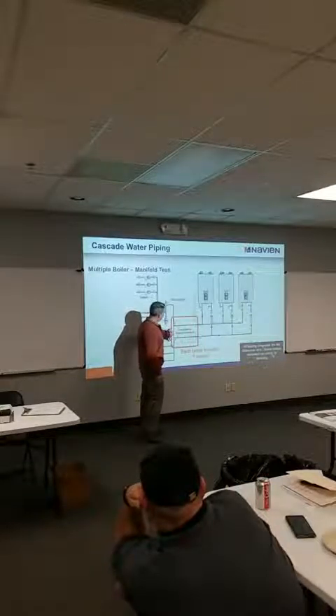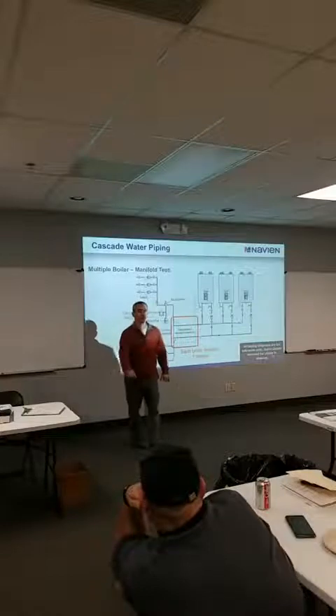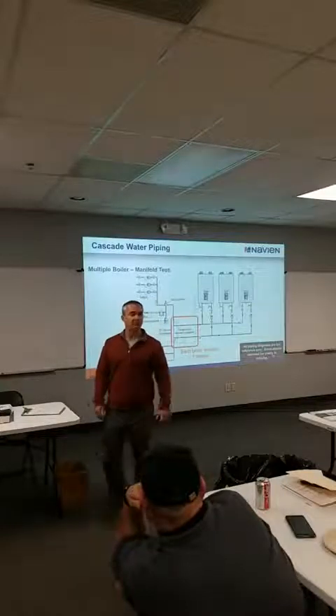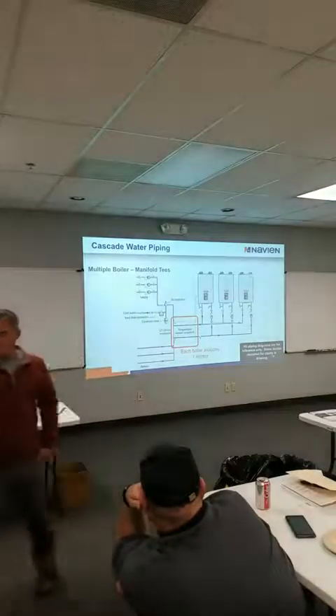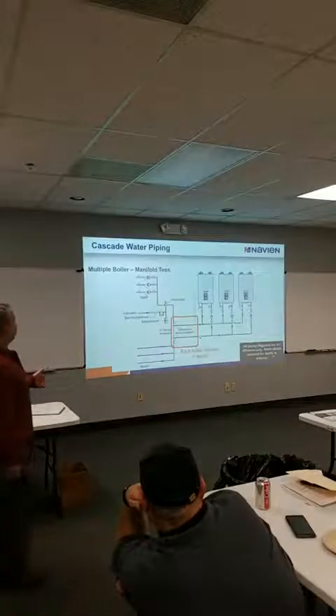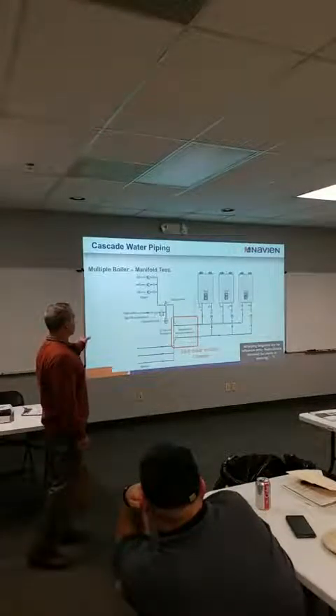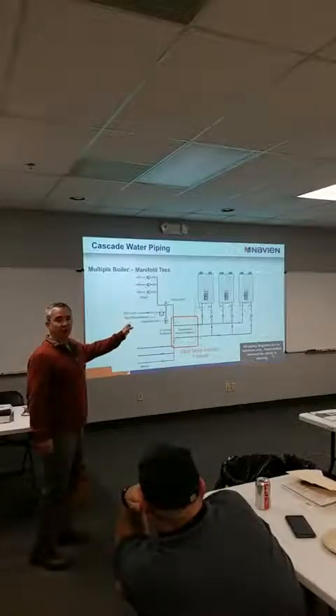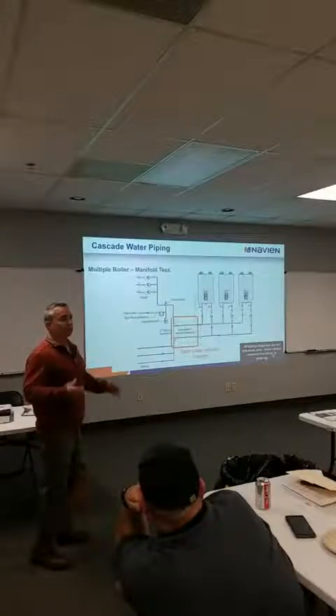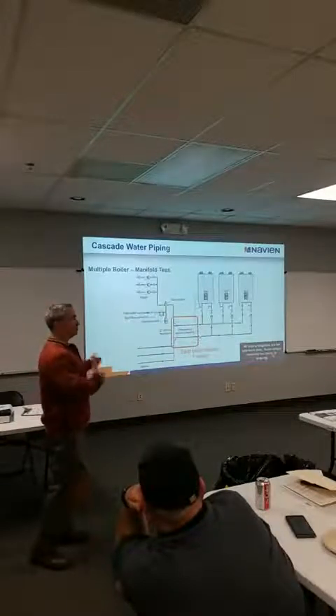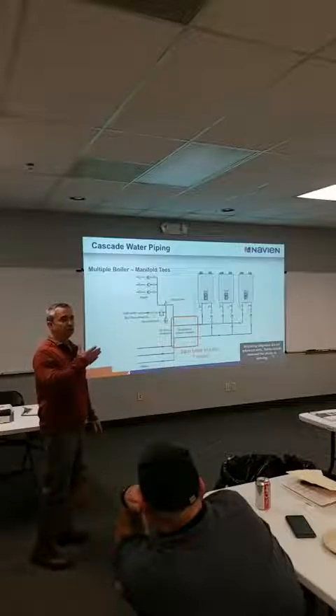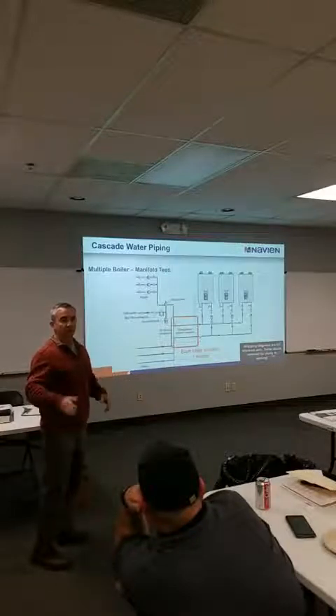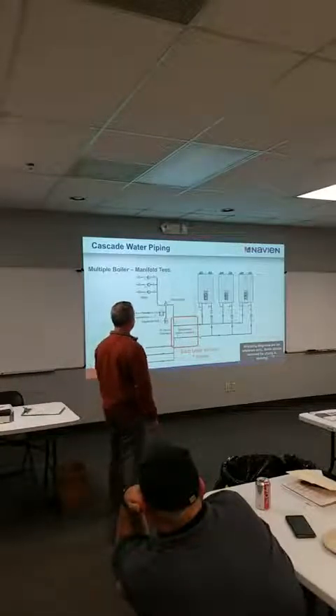Take these back to the main unit. You put them on your return supply main system piping, and then you can run the boiler off those temperatures instead of the boilers looking at the boiler temperature. When you're doing multiple boilers, they all want to look back and see what's going on in the system. So regardless of which one is running, it knows what the system is doing.